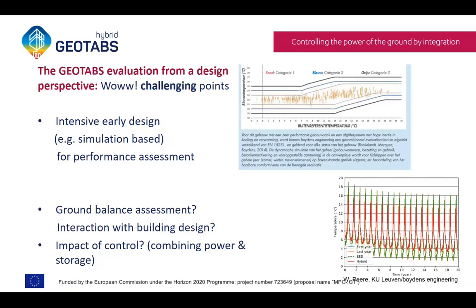Another one, a little bit related, is that you need to look at the ground balance. If you extract more heat in winter than you supply again in summer to the ground, then the temperature of the ground will go downwards. If it's the other way around, if it's a cooling dominated building, the temperature in the underground will rise.